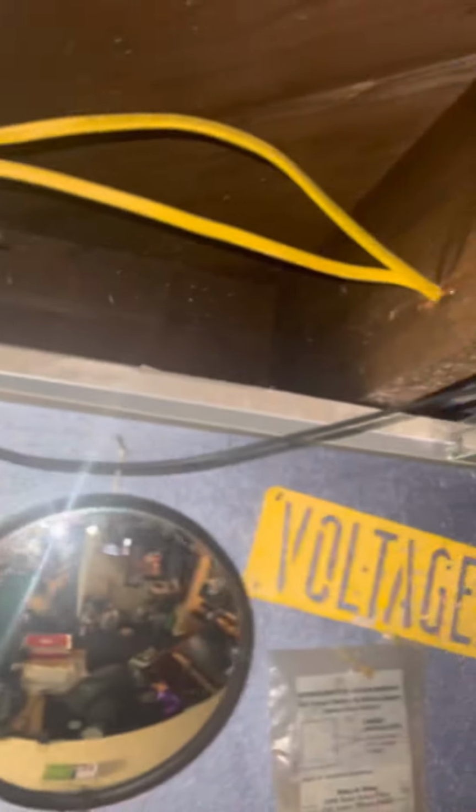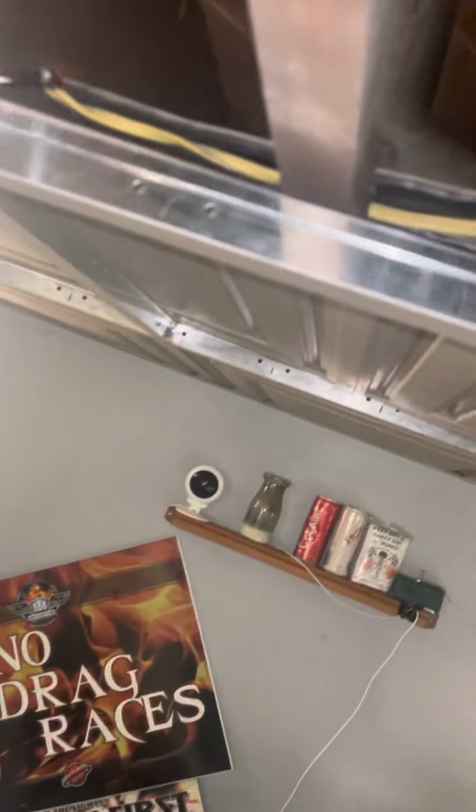It's just tremendous, and you can see, oops, whoa, blackout, what's going on? Oh, no. Yeah, that looks like no problems, does it? Look at that. I like seeing the new wire because it's all that yellow and you can tell in the panel. But the good work and the bad work, you can see it there. Most of the good work is the older wiring, which tells me that who did this work was not qualified. Look at all the twists in this wire right here.